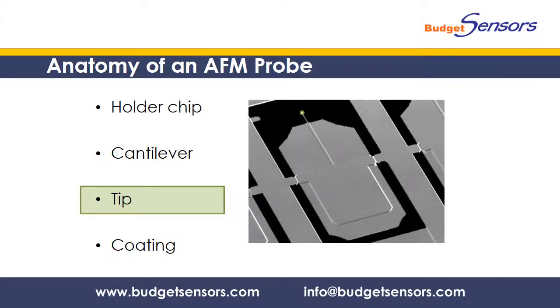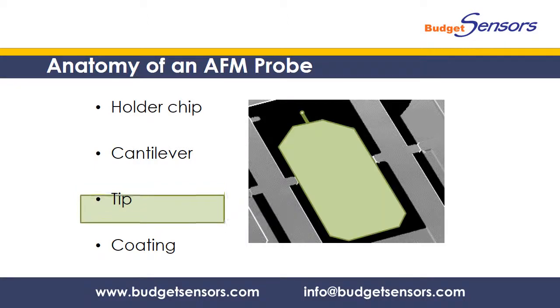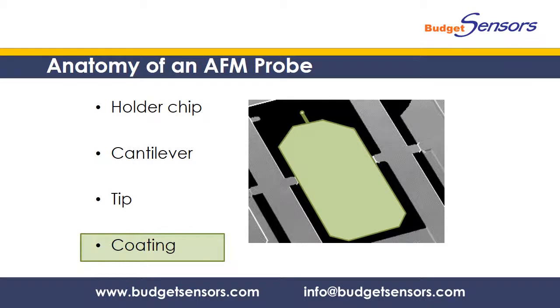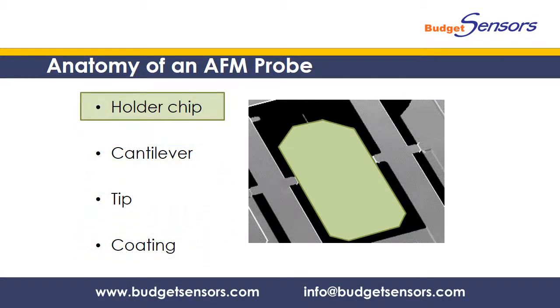The tip is hardly seeable on this image, but we will have a chance to take a closer look at it later. Finally, the AFM probe may have a coating on one or both sides of the chip and the cantilever. The purpose of this coating depends on the application. It could, for example, enhance the electrical conductivity of the probe, the laser reflectivity of the cantilever, the chemical stability of the probe, etc. There will be separate videos on cantilevers, tips and coatings. In this video I will just start with the easiest and most straightforward to discuss element, the holder chip.